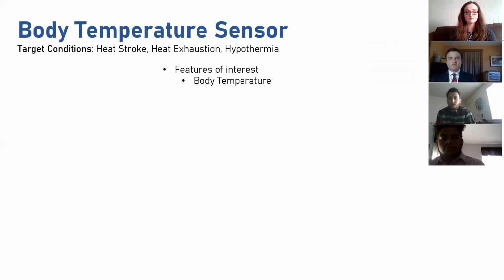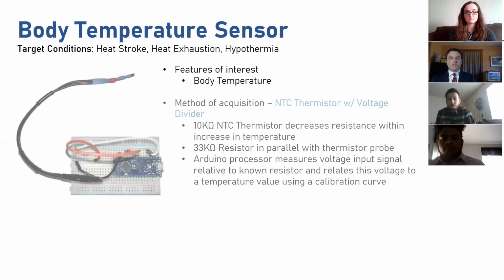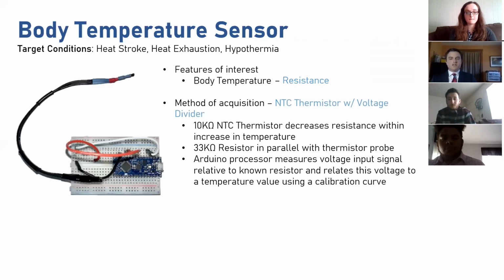The feature of interest for the body temperature sensor is body temperature being measured as a resistance. This is done using a 10 kilo ohm NTC thermistor, which is wired in a voltage divider. In this voltage divider, a 33 kilo ohm known resistor is wired in parallel with the thermistor probe. An Arduino processor is then used to measure the voltage across the thermistor pathway, and using a temperature calibration curve created, this can then be related to a known temperature.